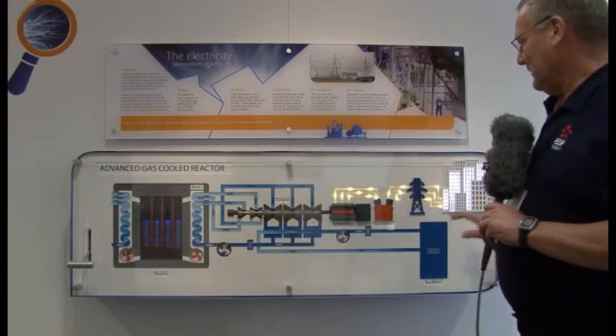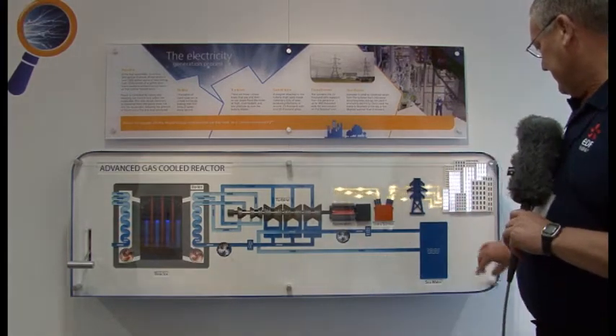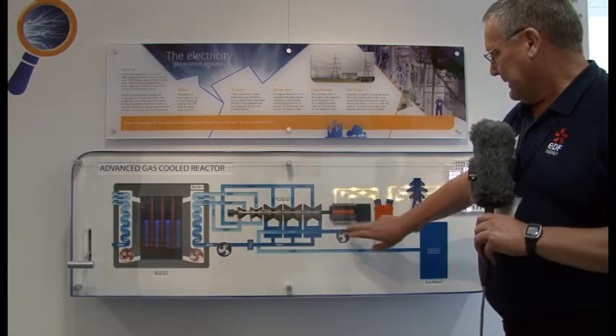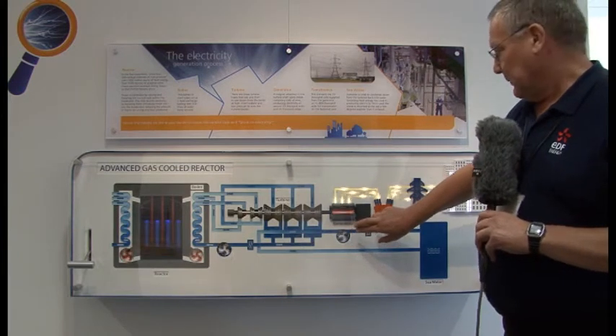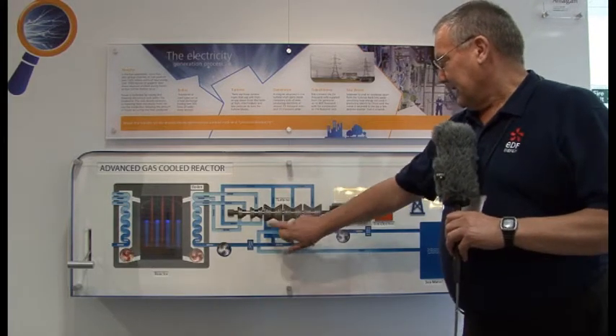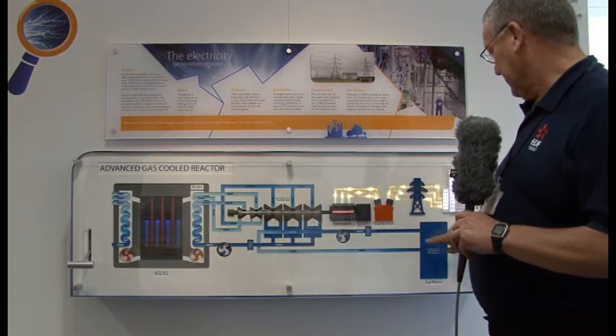This is a diagram of Torness Power Station. On the cooling water side, the cooling water is brought in from the sea through drum screen filters. It then goes through four main CW pumps, which send the sea water up to the condenser in the turbine area, and then it returns back to the sea on the far side of the station at the cooling water outfall.